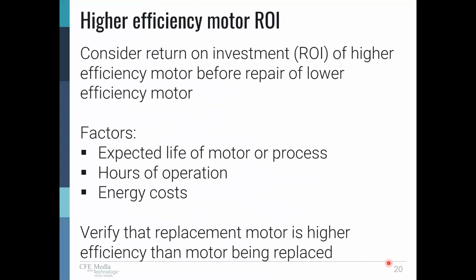So going back to repair or replace, consider the return on investment: the higher efficiency motor versus the lower efficiency motor, and the factors that are involved. The lifetime of the motor or the process. How long is it going to run? What's the cost of energy? If we have a motor that runs 24/7, in round numbers it's about 9,000 hours a year. If that motor is going to run for 10 years and that application is expected to last 10 years, now we've got 90,000 hours.